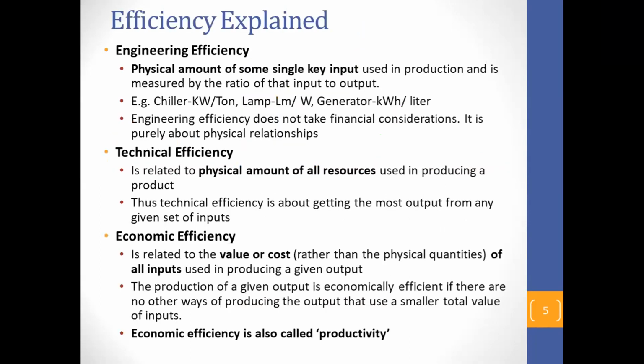And we call it engineering efficiency. A simple example is a chiller. We define chiller efficiency as kilowatt per ton. Now chillers are coming at even less than 0.5 kilowatt per ton. When I was leaving the university, chillers were operated at 0.8 kilowatt per ton, 0.8, 0.85, and it can be even worse than that. New chillers are operating at even 0.4, 0.45, very efficient. So this is called engineering efficiency.